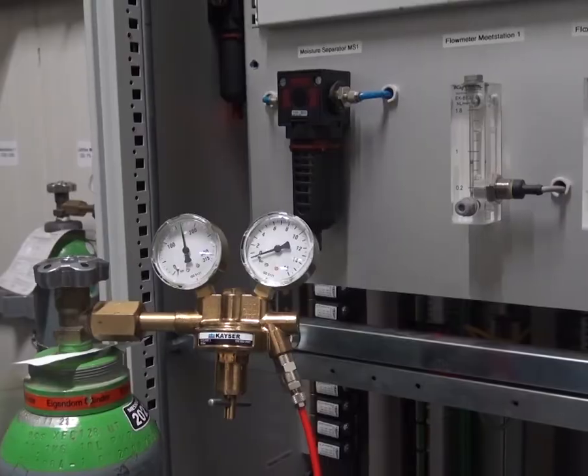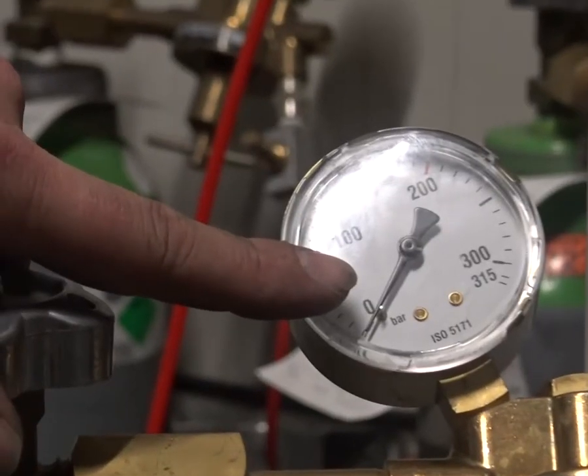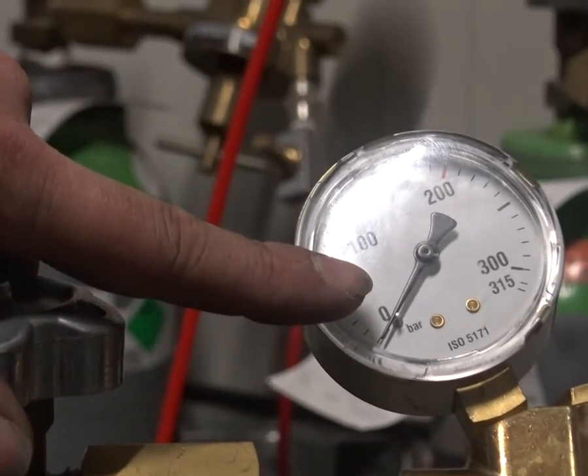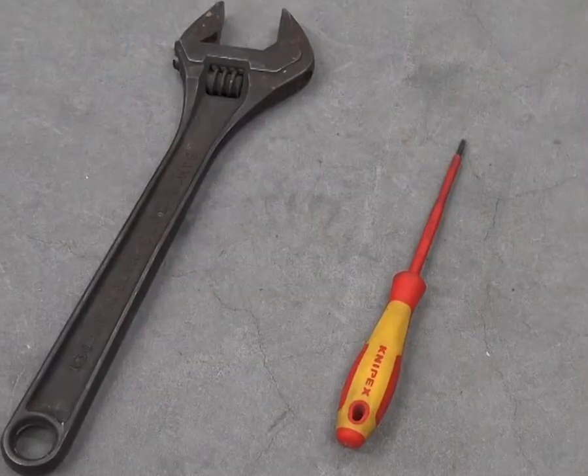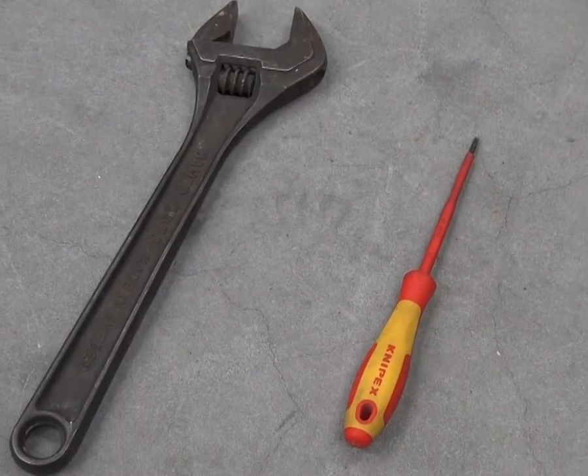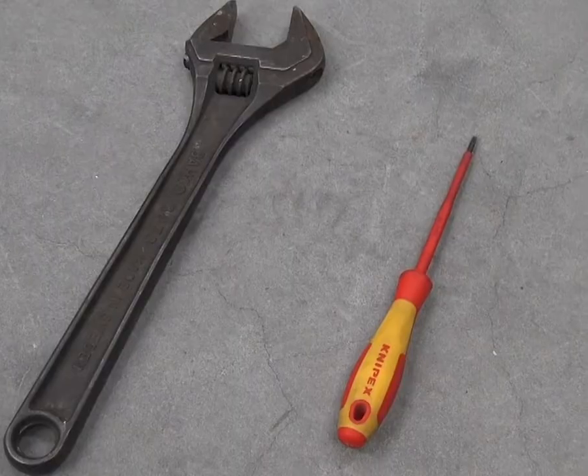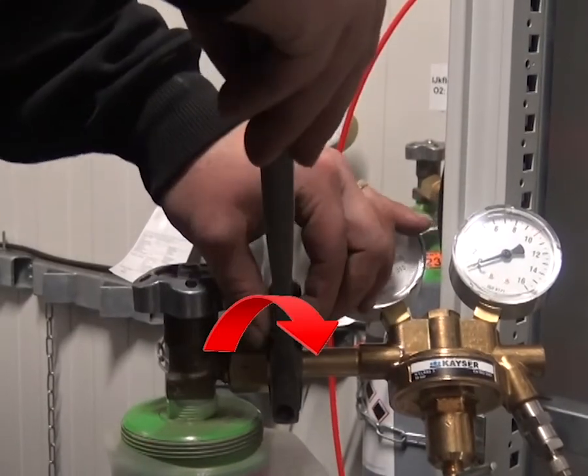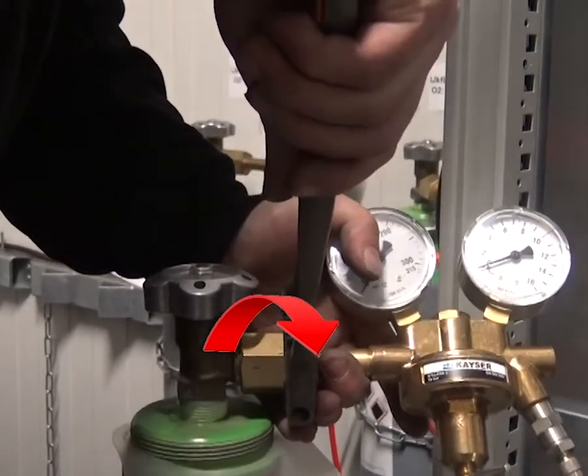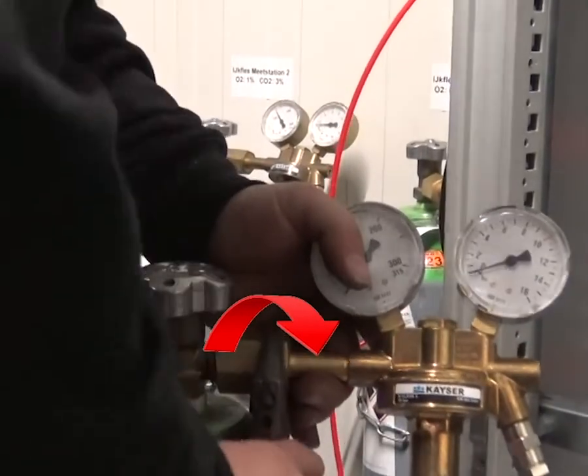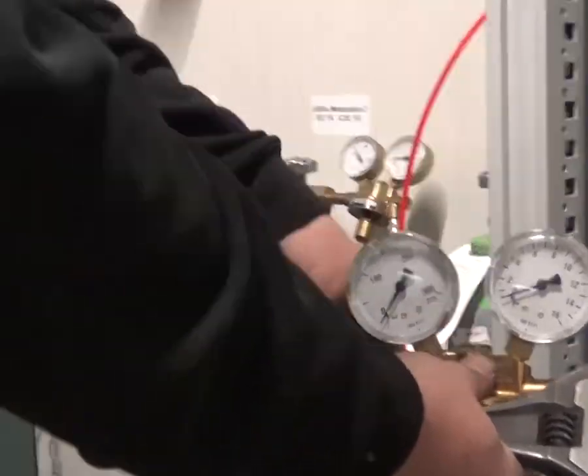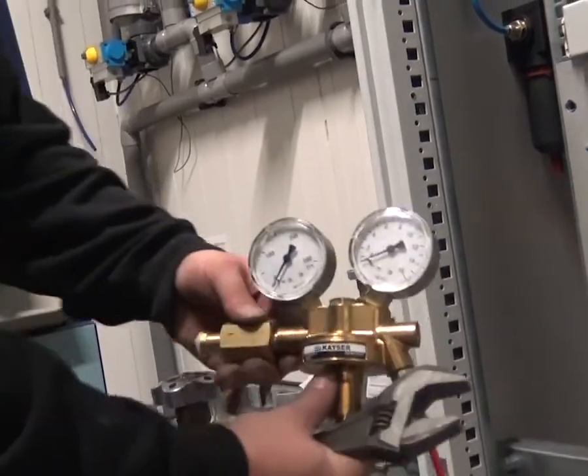Check on the calibration gas bottle if the meter reads 0. This means that the calibration gas bottle is empty. To replace the bottle, you will only need an adjustable spanner and a screwdriver. We will now demonstrate how to replace the empty gas bottle. Close the empty bottle and grab the connection with the adjustable spanner and unconnect the reducer from the bottle.